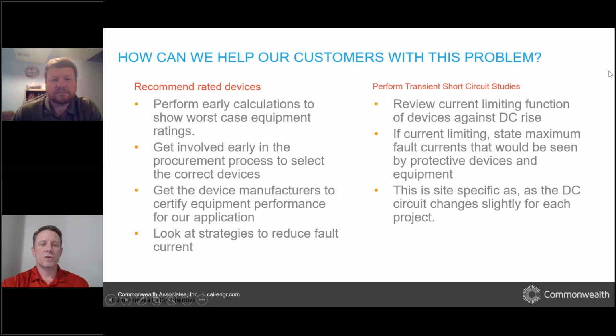There's a number of things we can do to try to help the high fault currents and the high arc flash. The easiest way is if we get in early and we can help specify the equipment and the design. If we can't get in early enough in the process to do that, we can still look for strategies to reduce it later, but sometimes it might be a little bit of a redesign, and it could be more painful if you don't do the studies in advance. Doing the studies in advance also has the same problem of getting the equipment or getting the information to do the studies, because it doesn't exist yet. You're trying to get the specifications from manufacturers to do the studies. So there's a little bit of a chicken and the egg thing there.